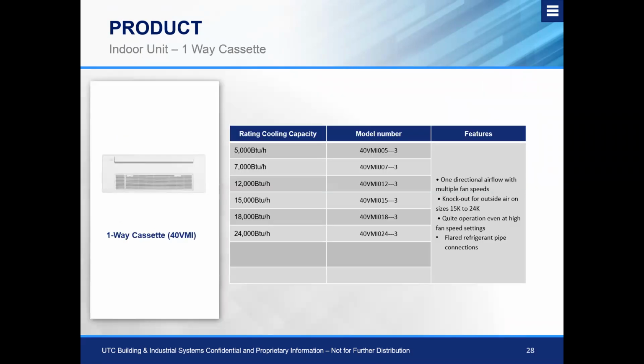Now, specifically on our one-way cassette, which is a new product introduction, we can range from 5,000 all the way to 24,000 BTUs of capacity. So of course, with the one-way cassette, we have that one directional airflow with multiple fan speeds. And a unique feature with this one is we have a knockout for outside air, which of course has to be pre-treated. But for sizes 15,000 all the way up to 24,000 BTUs, we can facilitate piping in some outside air that is pre-treated to the actual fan coil itself.